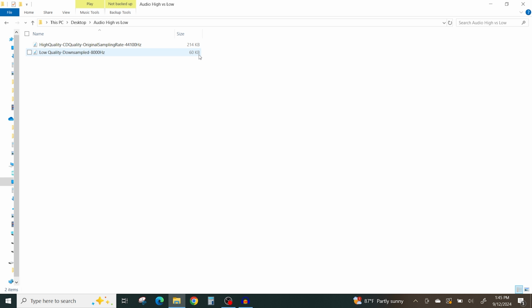You could sort of equate this to phased array. If you're scanning with a higher digitization frequency, or, what we'll talk about in a minute, if you're using less compression, you're going to have a bigger file size, and it's actually going to take you longer to acquire that scan because you're getting more data. If you use a lower digitization frequency and sampling rate, or if you do more compression, you're going to acquire less data. So your acquisition rate would be a little bit faster in this case. So we'll talk about compression with phased array here coming up next.